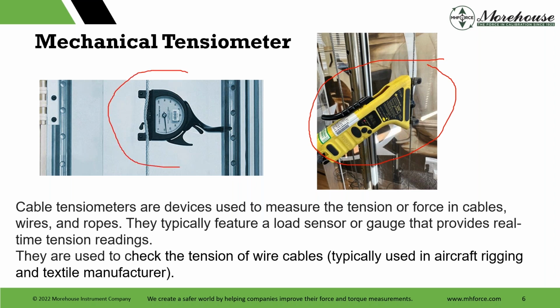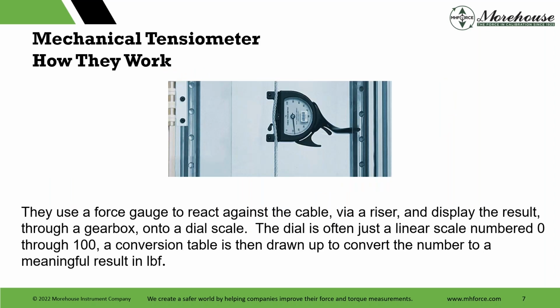these analog ones. And you can see here, which is interesting, in this picture, look how the cable's bending more as we clamped onto it. So that's going to have an impact on our readings with 2 fixed points, which we'll get into later. And typically what we're going to see the most is pilots flying. The more people I talk to, it's that industry, fly by wire. Most often you're going to control a rudder or something else with these cables, and if they're too tight, the pilot might complain, or you could have devastating impacts.